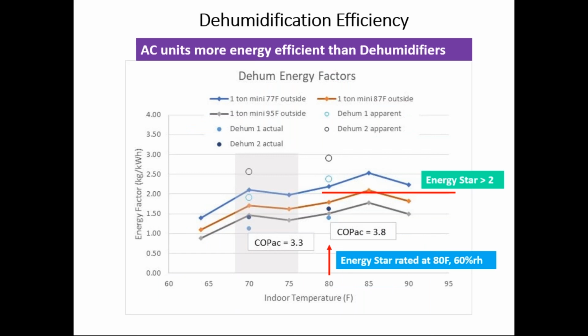And if we look at dehumidification efficiency, what's called an energy factor, it's basically the kilograms or liters per kilowatt hour of electricity running that dehumidification process. The open circles show the dehumidification energy factor for two very high quality dehumidification units. The rating point for Energy Star is 80 Fahrenheit with 60% humidity. You can see these two units have about a 2.4 and close to a 3.0 energy factor. But 80 degrees and 60% isn't typical where people would keep their homes. It'd be more in the, say, 70 to 75 degree range with a lower humidity.